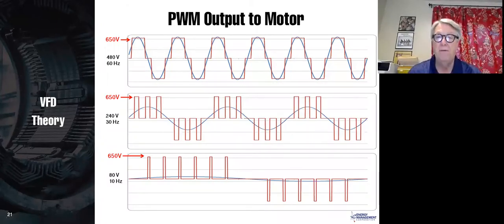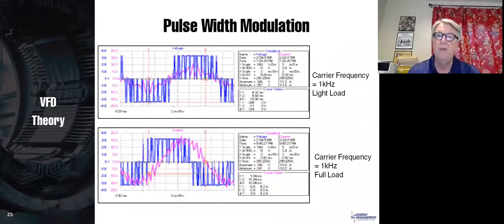So we have 10 hertz, and in my graph, 1, 2, 3, 4, 5, 6, 7, 8, 9, 10, 11, 12. There are 12 pulses in each cycle. 12 pulses per cycle times 10 cycles per second gives you 120 pulses per second. And that frequency is called our carrier frequency. The waveforms that I showed you, I just did on the computer. Now let's look at some real waveforms on a real drive.